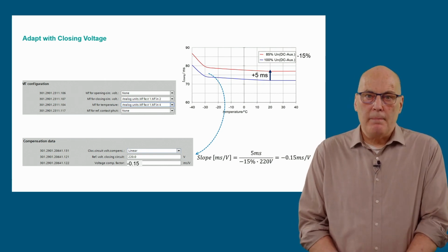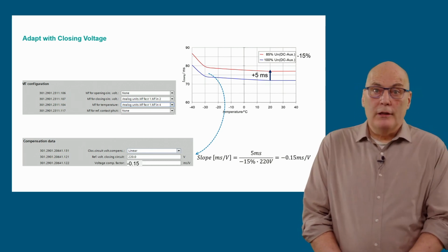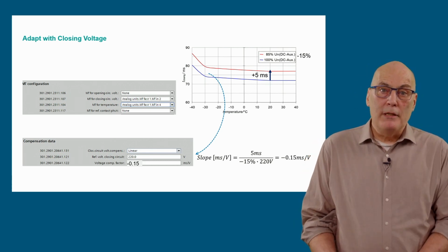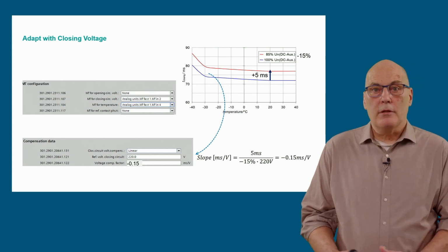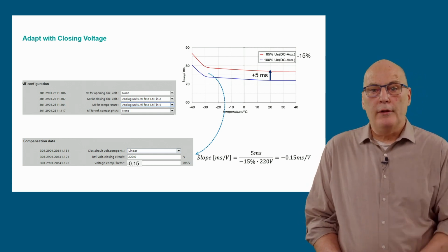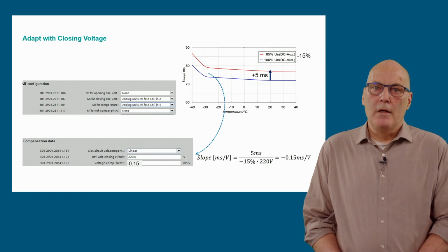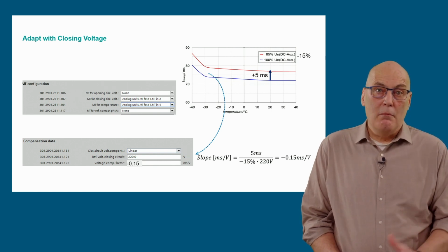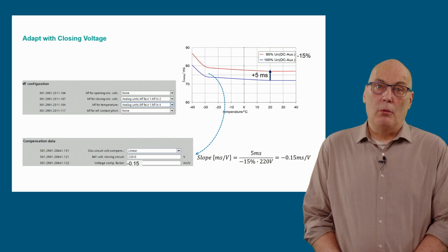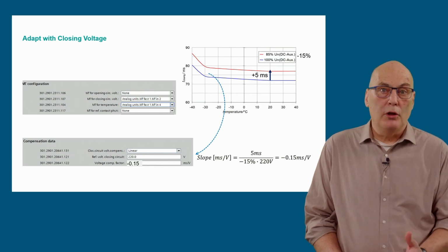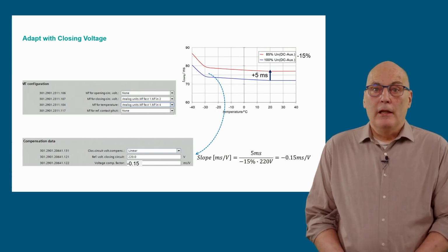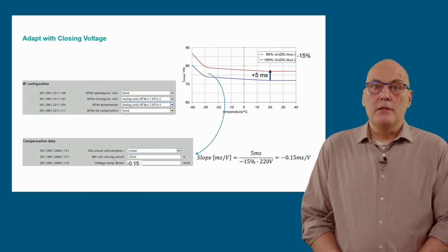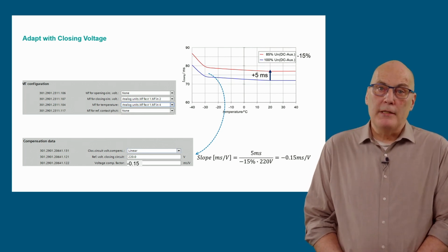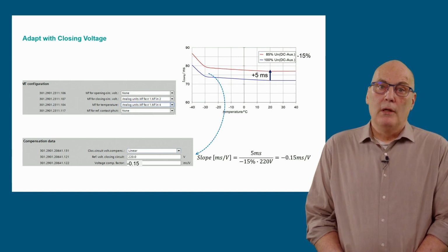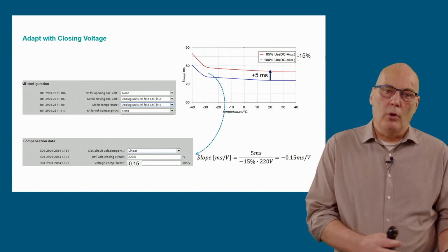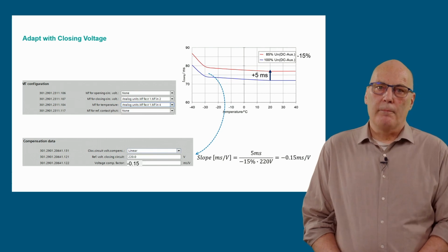20 degrees C. In this case, the delta closing time is approximately 77 milliseconds minus 72 milliseconds equals 5 milliseconds as shown in the diagram. The voltage difference is minus 15% of nominal closing voltage, for example, 220 volts DC. The equation returns a slope of minus 0.15 milliseconds per volt in this example, which can be then set as shown in the bottom of the diagram on the left.